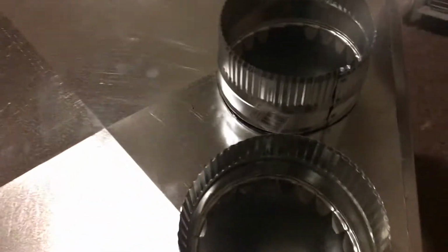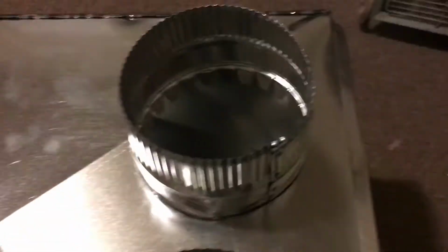By the time I made it to this side of the plenum, I'd gotten a little better with my tin snips technique, so my 2 holes here are a little neater, and my 6-inch takeoffs fit right in there, though one's squished a bit. I do have the bucket of mastic in that Lowe's bag over there to seal these in, but I won't be able to get the plenum set in place with those attached. So I'll have to just go ahead and set the plenum and then attach those.